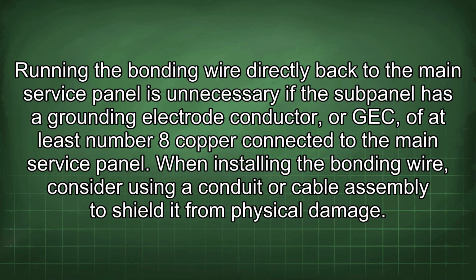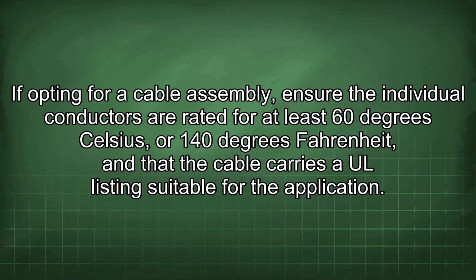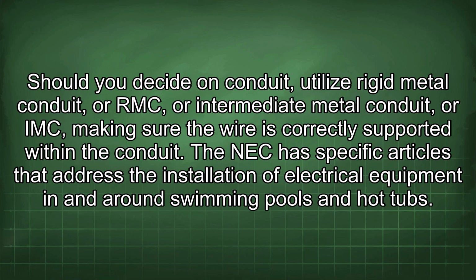When installing the bonding wire, consider using a conduit or cable assembly to shield it from physical damage. If opting for a cable assembly, ensure the individual conductors are rated for at least 60 degrees Celsius or 140 degrees Fahrenheit, and that the cable carries a UL listing suitable for the application. Should you decide on conduit, utilize rigid metal conduit, or RMC, or intermediate metal conduit, or IMC, making sure the wire is correctly supported within the conduit.